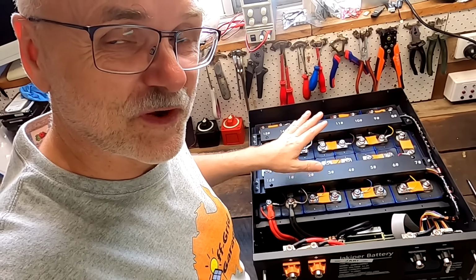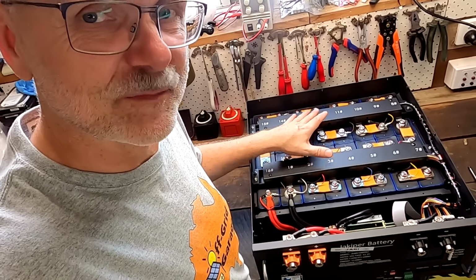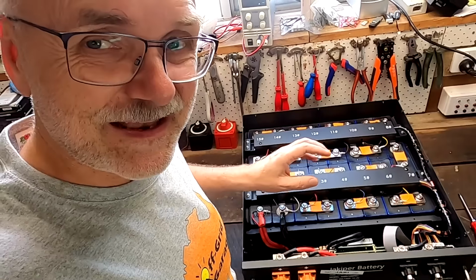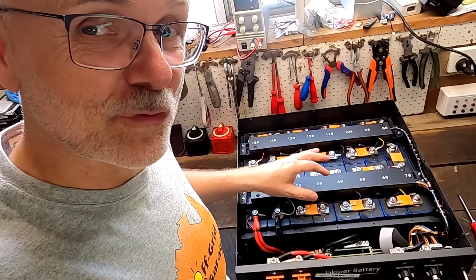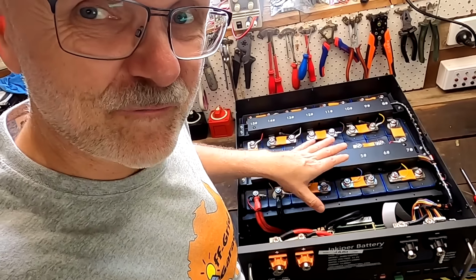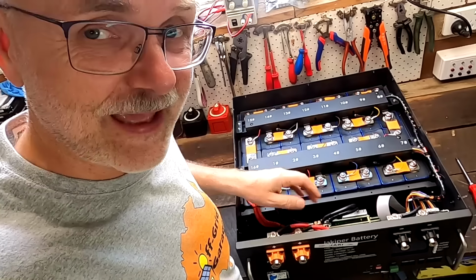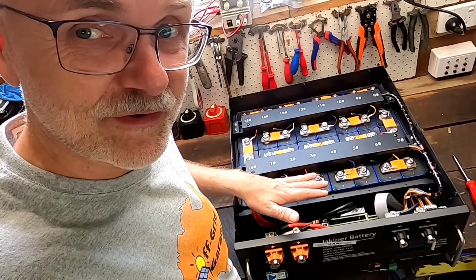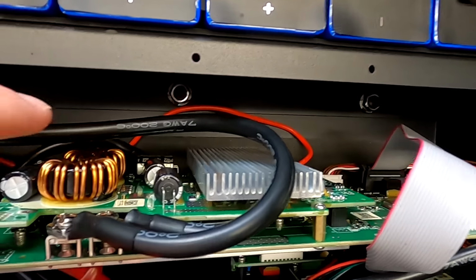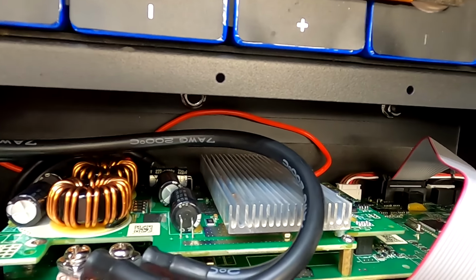So, from what I can see right now, this is one of the best batteries I've ever seen. Clean layout, well thought through design. All cells are in a fixture with flexible bus bars. Cable sizes are okay for the rated current, and we've got a large PACE BMS in here with even a current limiter.